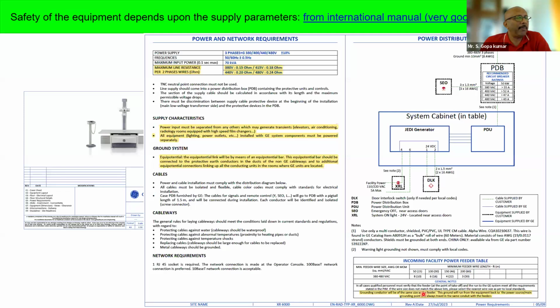Also in several places of the manual, for example, the grounding conductor will be of the same size as the feeder. Please note that this document is from USA, so instead of earthing, they use grounding. The ground will run from the equipment back to the power source main grounding point and always travel in the same conduit with feeders. Please read it seriously. The ground, that means the earth, the protective earth conductor, will run from the equipment back to the power supply source. The source can be a UPS or a DG or a transformer.